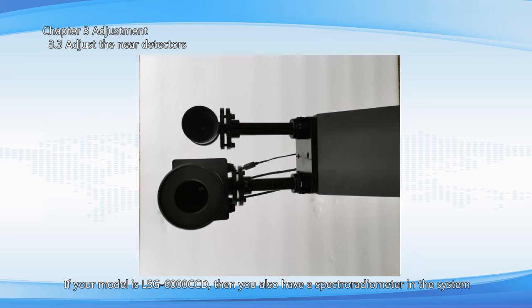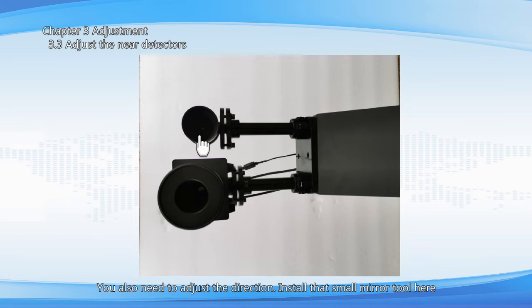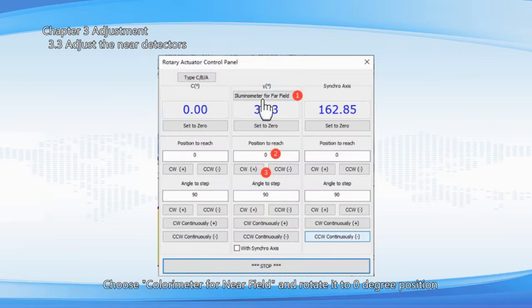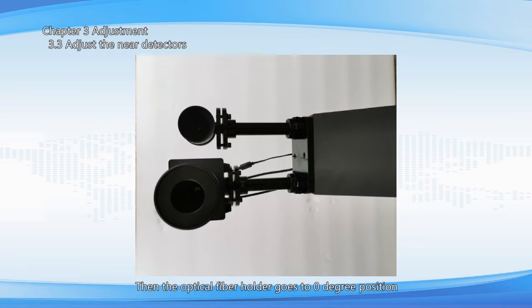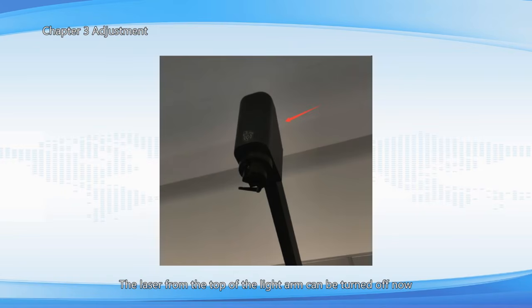If your model is LSG-6000 CCD, then you also have a spectroradiometer in the system. And there will be the optical fiber holder here. You also need to adjust the direction. Install that small mirror tool here. Choose colorimeter for near field and rotate it to 0° position. Then the optical fiber holder goes to 0° position. Do the same adjustment as you did for the near photo detector. The laser from the top of the light arm can be turned off now.